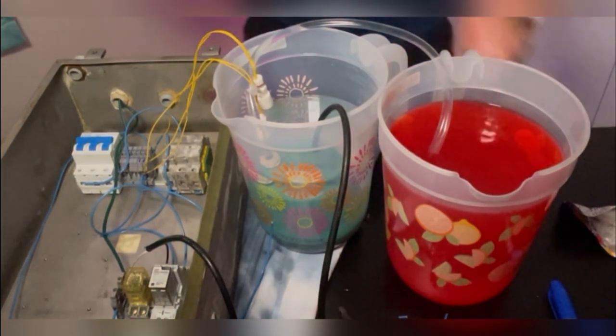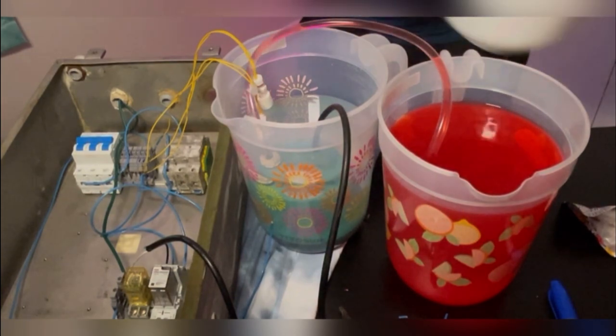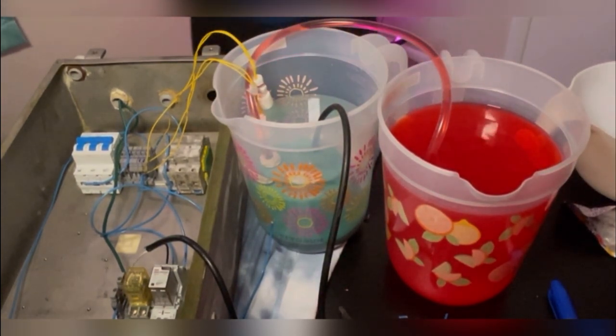Rinse and repeat. There's your float switch controlled lift station, pumping station. Let me turn this up. Hopefully you guys can see me pretty good. Obviously the floats are going to fail. Things are going to fail. So a lot of times you'll have alarm monitoring. Good way to produce an alarm for a system like this. Say you don't want your tank to overflow. What you would do is put another float in there. You call it your high alarm float. Make it higher than the rest of them.